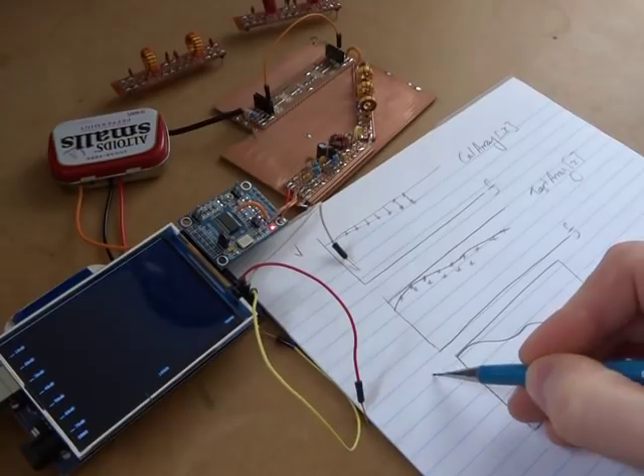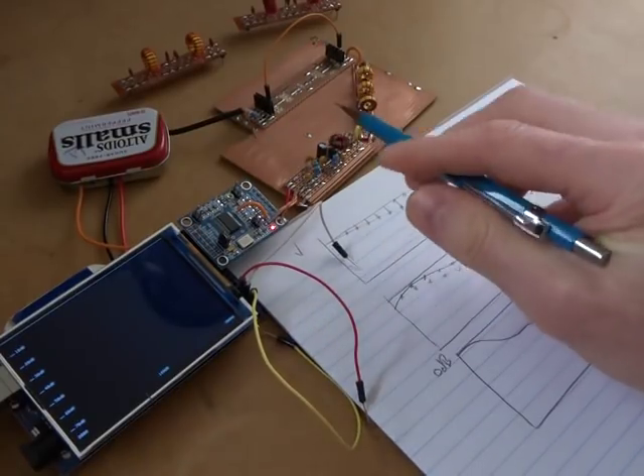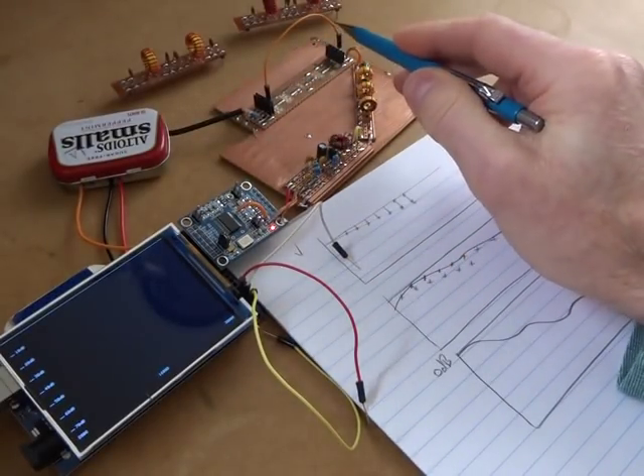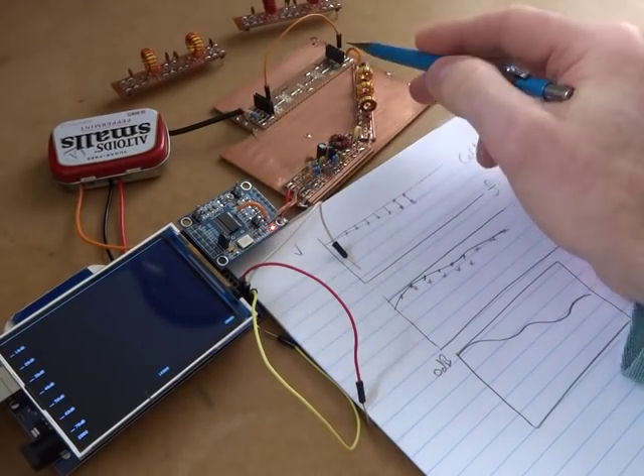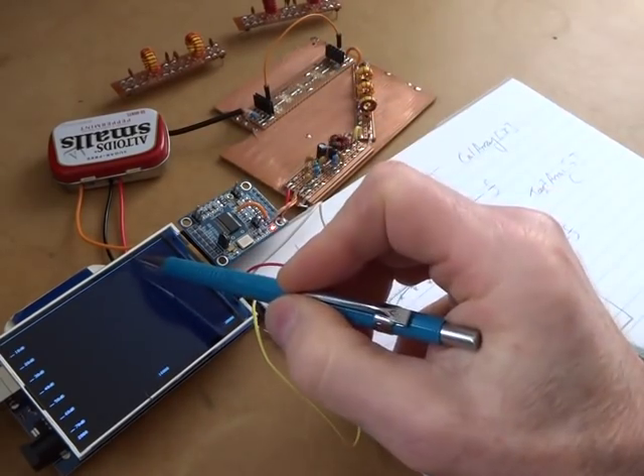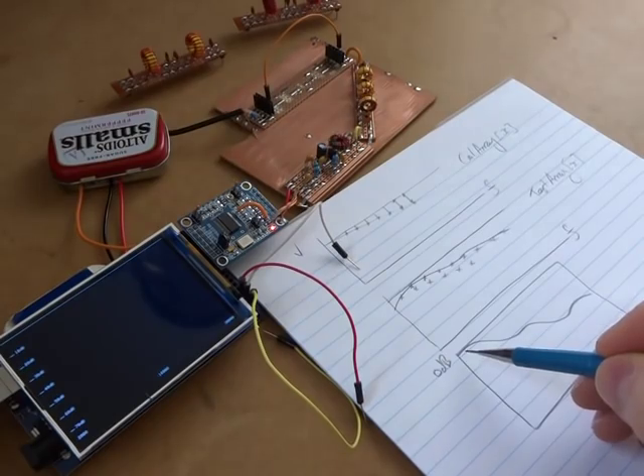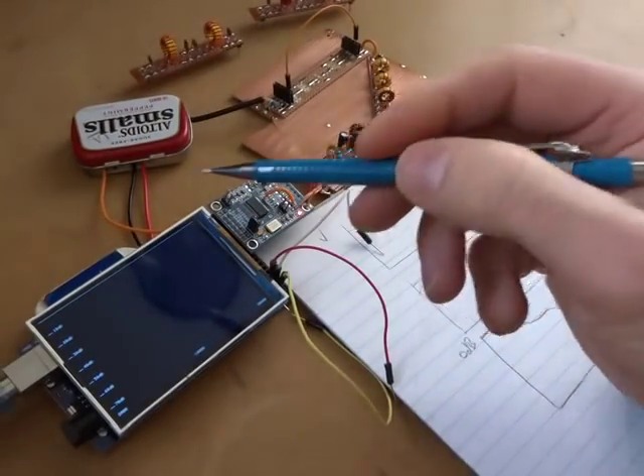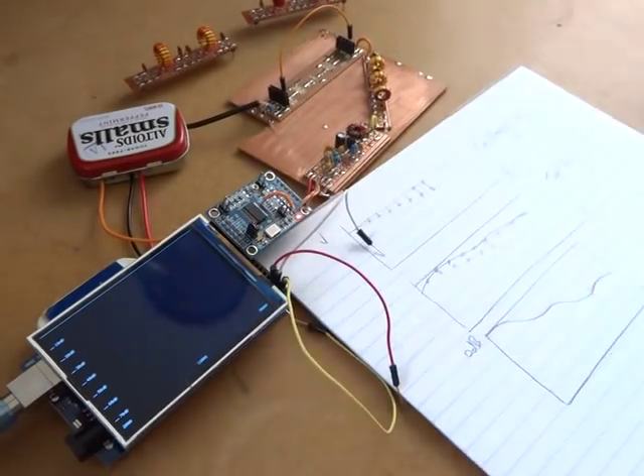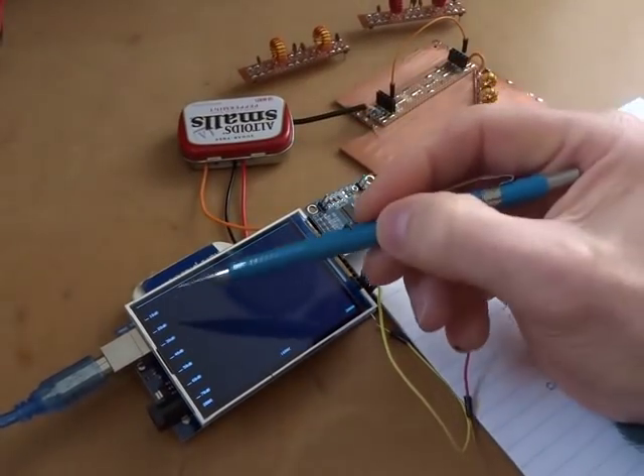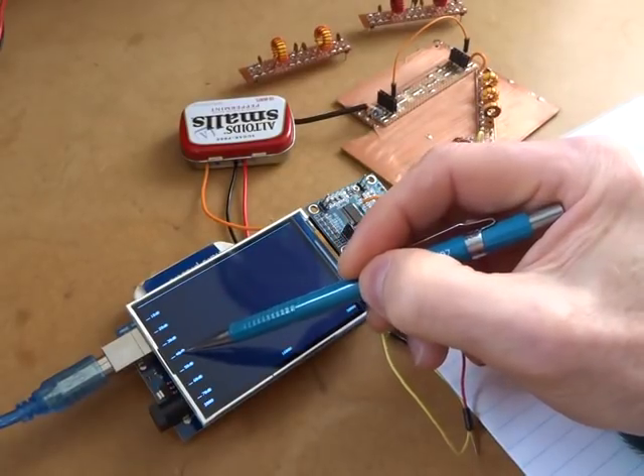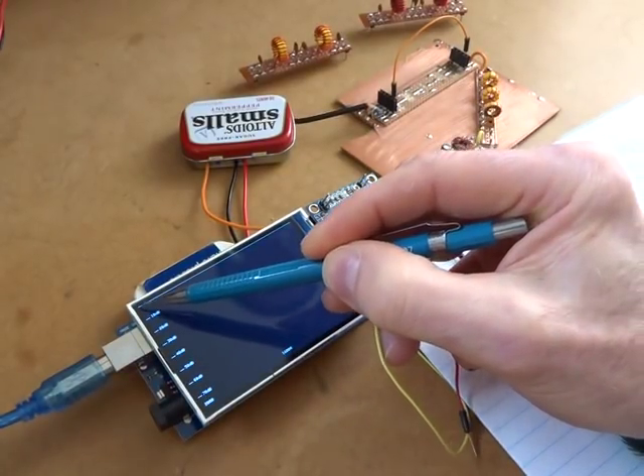I want this to be 0 dB, so in other words we've got a straight linkage there, effectively 0 attenuation, so I want to be at the top of the screen, which is here. And then, oopsie daisy, apologies. Down the left hand side we've got a series of tick marks: minus 10, 20, 30, 40, 50, 60 dB, and they're calibrated.